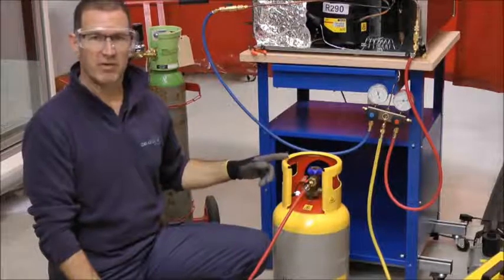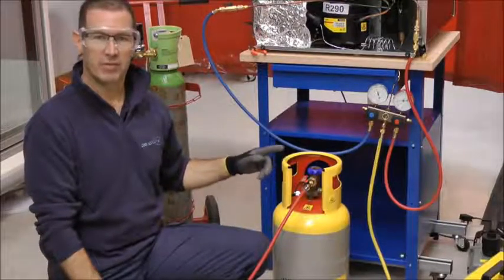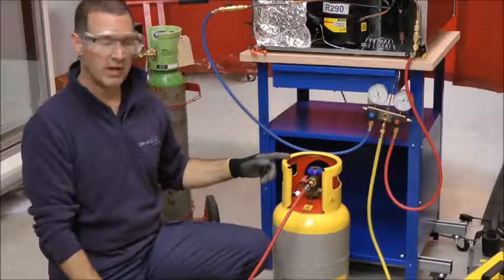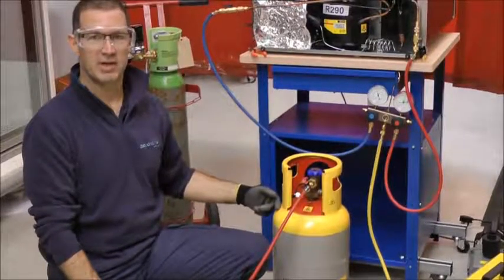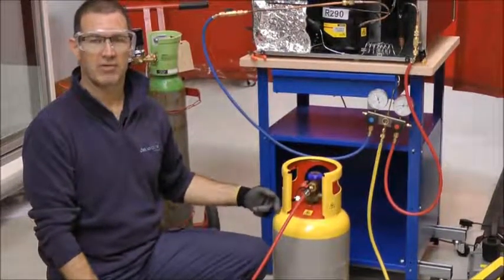The consideration we have to make with the recovery cylinder is the density difference that we've already discussed outside of this video. In our case here, this standard 10 kilogram recovery cylinder will take four and a half kilograms of hydrocarbon refrigerant.